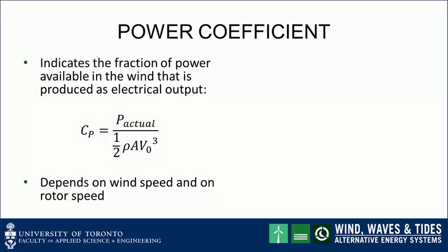The most important measure of wind turbine performance is the power coefficient. The power coefficient indicates the fraction of power available in the wind that is produced as electrical output. In the equation, the numerator, p-actual, is the actual electrical output produced by the wind turbine, while the denominator contains the very familiar one-half rho A v-cubed, which represents the power available in the upstream wind.